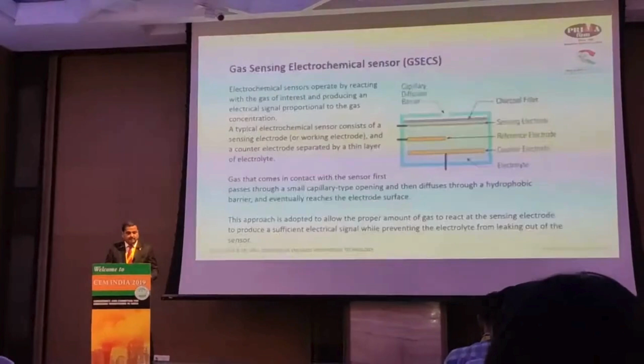I would like to narrate again, but if I share my experience of 27 years of using this technology, these sensors are considered to be the most efficient, very fast responsive, and the most important part, which I'll come to on the next slide, is that they are 100% linear. So here we can have a 2-point calibration. That's more than enough. And the stability of the linearity, we consider as more than 4 months to 6 months. A plus point is that you have a high range of SO2 measurement. You can go up to 5,000 ppm measurement without any dilution or anything to be done here. You can straightaway choose that.